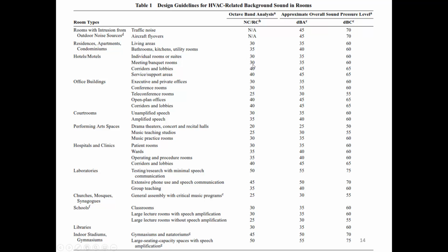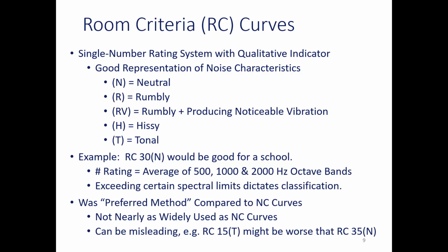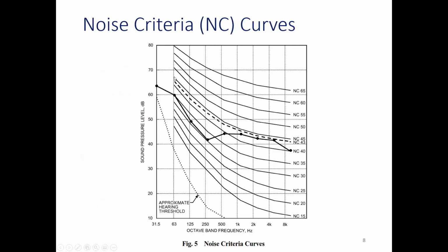Actually, if you're at NC 30 and it's being driven by lower frequency, you might go up 1 decibel and it's different. I think we had that, didn't we? Yeah, here. This isn't 5 decibels here, you're going up 5 NC. Here, it's more truly 5 decibels, but over here, it's not. You're going from NC 50 to NC 55 in just 2 to 3 decibels. So say you went up 1 here, that might raise your NC rating 2 dB. But your dBA, if it was this noise spectrum, raising this up 2 might not affect your dBA at all, because your dBA is probably going to be driven by these, and then that curve comes up like this.